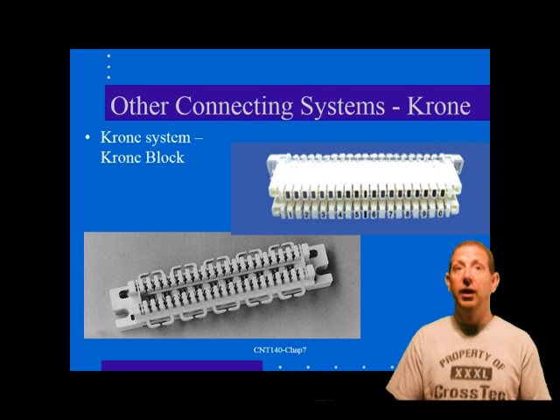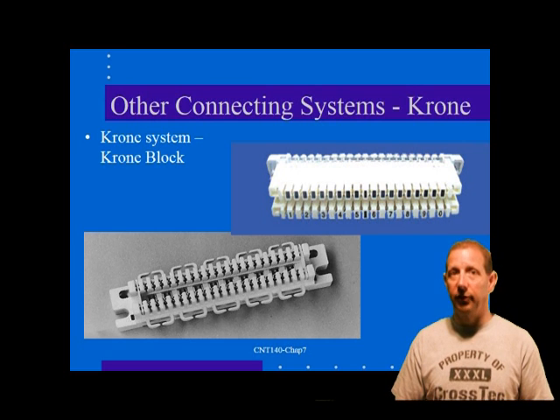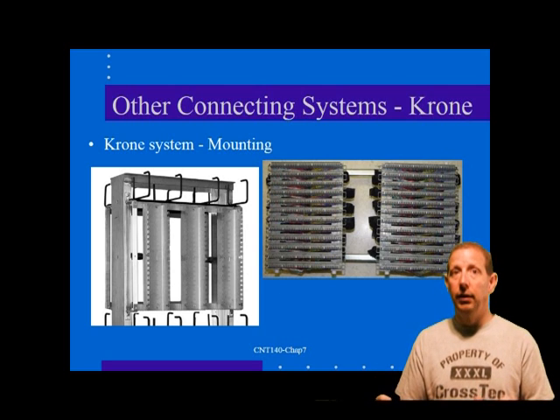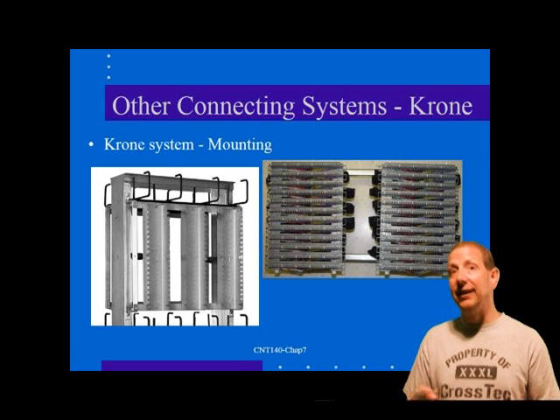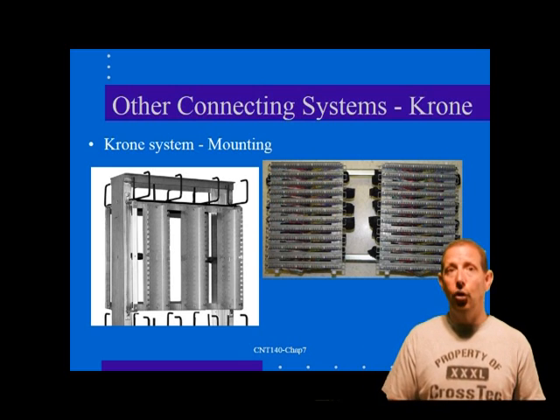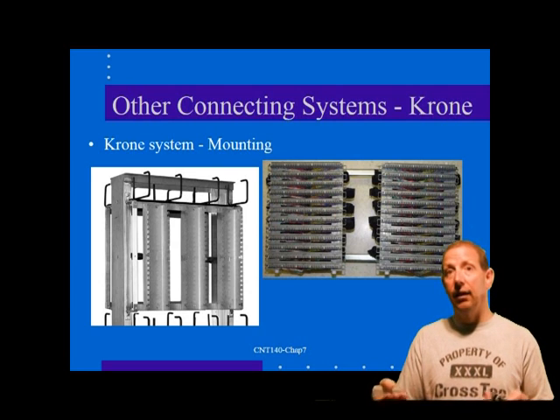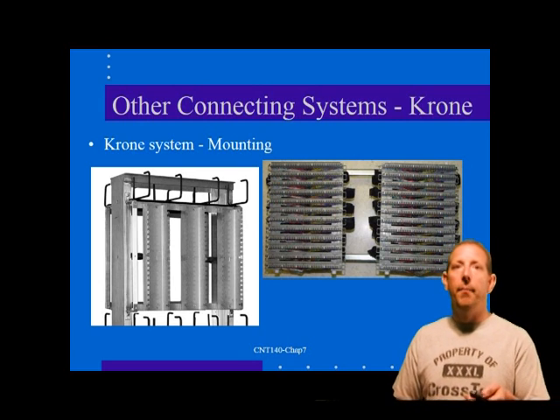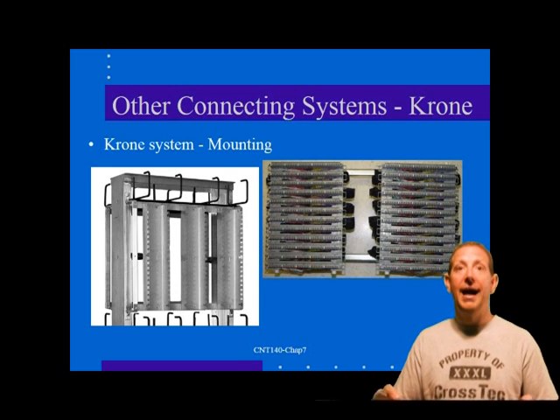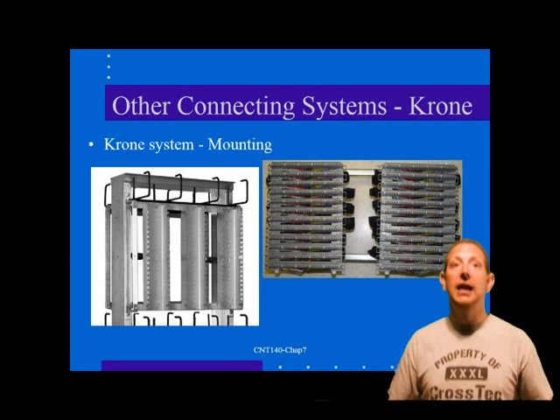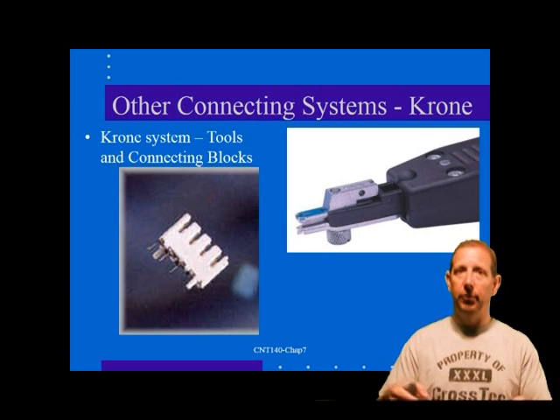Krone assemblies also mount in distribution frames intended for 66 blocks, and the availability of 66 type mounts means versions of the block can be offered with integral 50-pin telco connectors, just as with the 66 blocks. Station and cross-connect wires are terminated on the bottom and top respectively of a Krone connector. The connector offers a unique disconnect contact as an option, and connectors with the disconnect feature can be temporarily opened for isolated testing of either leg of the circuit. Krone connectors may also be found in outlet jacks and patch panels for wire termination, and many manufacturers offer the Krone wire termination system as an option. The connector hardware may be certified to CAT5E and 6, but the usual guidelines for wire pair terminations must be observed.